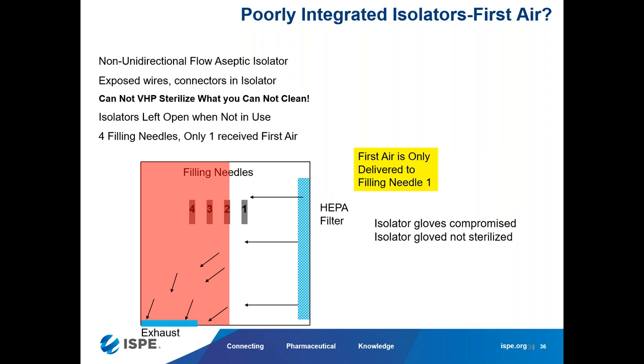The FDA loved the product but did not give them the blessing to manufacture the product. Why? We talked about this before. First air to the filling needle, important. HEPA filter is on the side. Which needle gets the first air? The first needle. There is no assurance that any other needle will get first air.